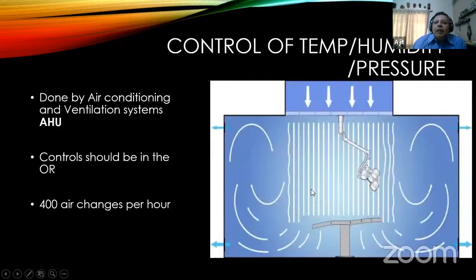How do you control the temperature, humidity, and pressure? This is done by the air conditioning and ventilation systems, or the air handling unit. The controls should be inside the operation theatre, so in a modular theatre, each OT can adjust its own temperature and humidity. 400 air changes per hour is ideally described for an operation theatre, and this is still without considering laminar airflow, which forms a separate part of my talk.